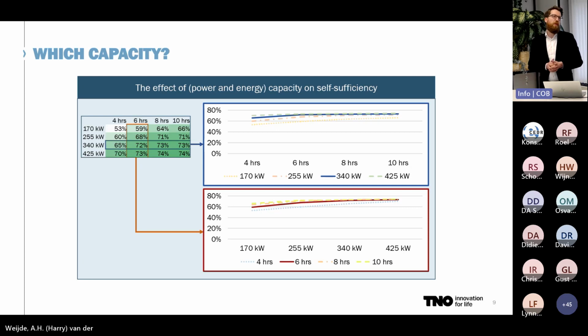That also doesn't help you much. It helps a little, because there are some hours during the year when there's an emergency and the entire ventilation system of the tunnel is on, so that's why you might go from 72% to 73% self-sufficient, but that comes at a fairly major cost. For this particular tunnel, 340 kilowatts with 6 hours of storage capacity is the sweet spot. Going much further than that doesn't make much sense, since it doesn't bring additional self-sufficiency, so that's the capacity we'll use for the rest of the analysis.